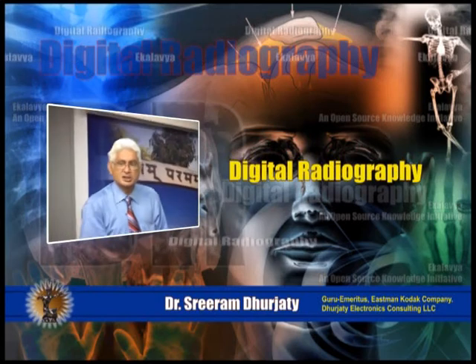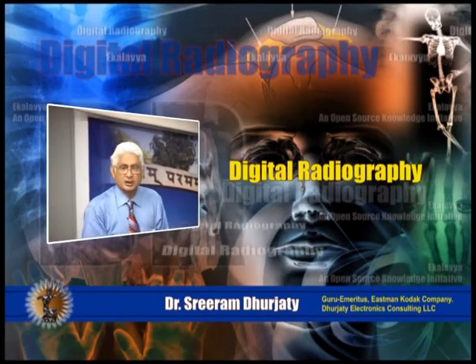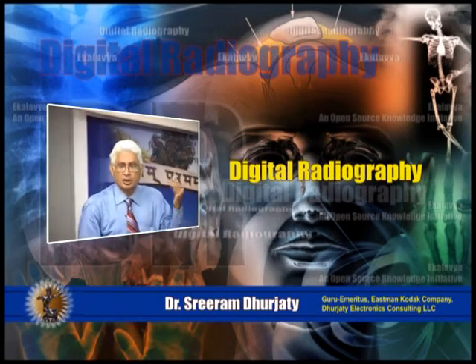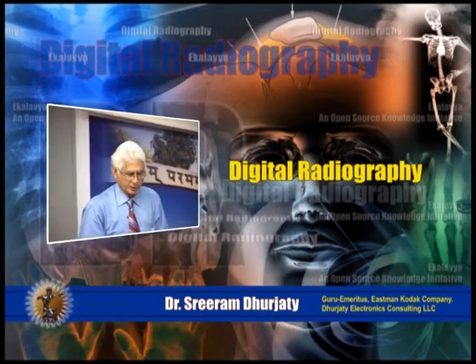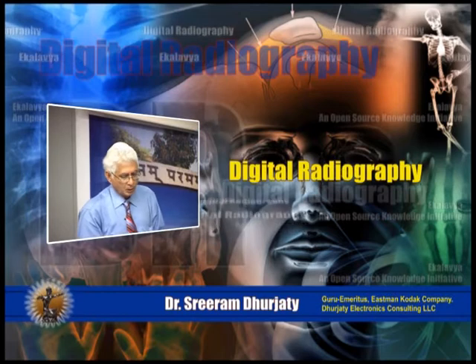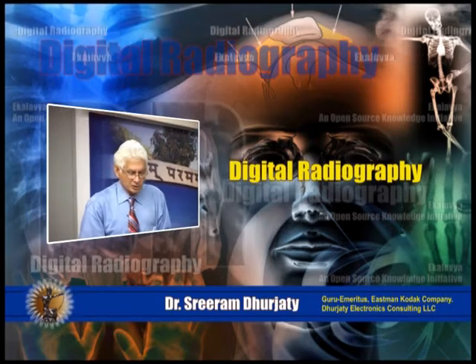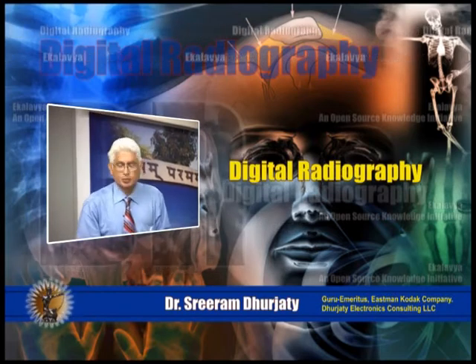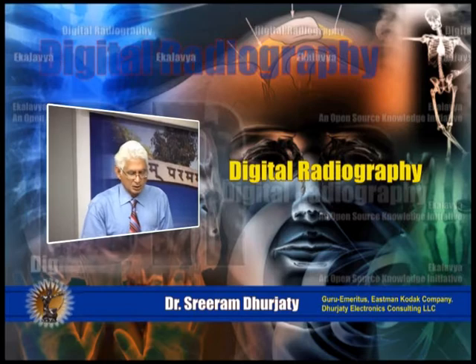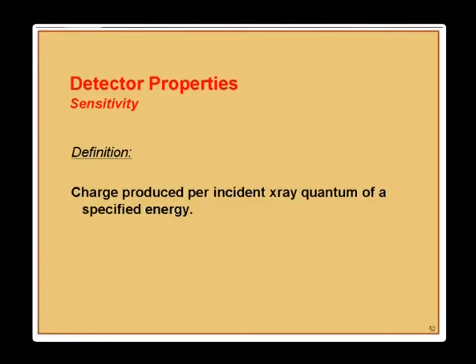What is the sensitivity of a detector? We define sensitivity as the charge that is produced per incident X-ray quantum at a specified energy, because the sensitivity can be different at different energies.